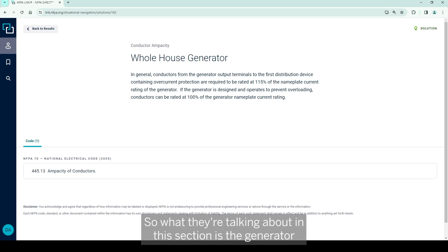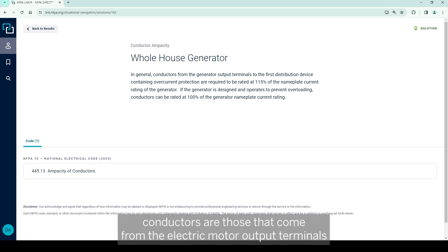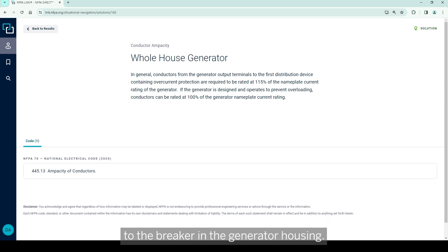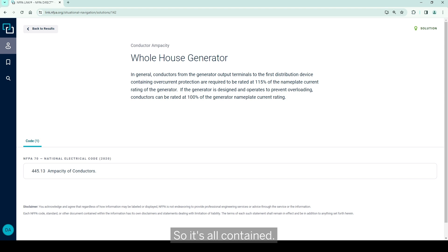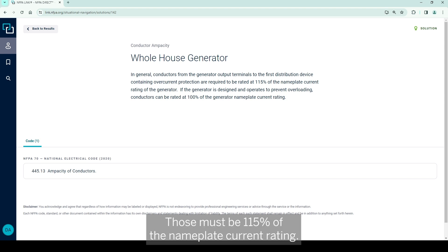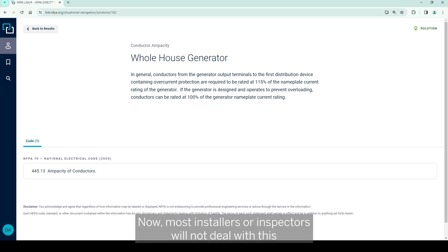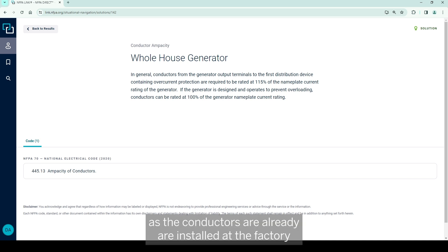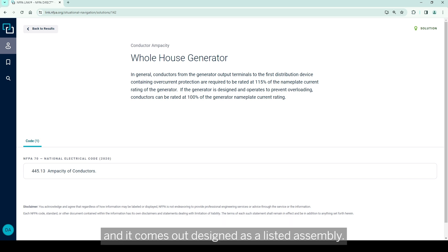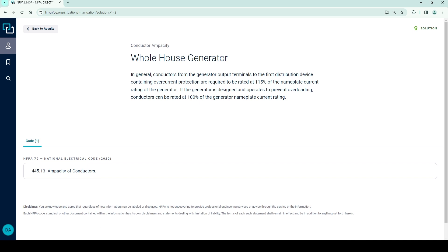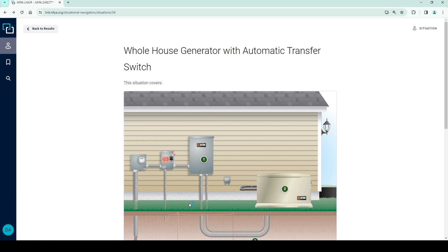So what they're talking about in this section is the generator conductors are those that come from the generator output terminals to the breaker in the generator housing, so it's all contained. Those must be 115% of the nameplate current rating. Now, most installers or inspectors will not deal with this as the conductors are already installed at the factory and it comes out designed as a listed assembly.